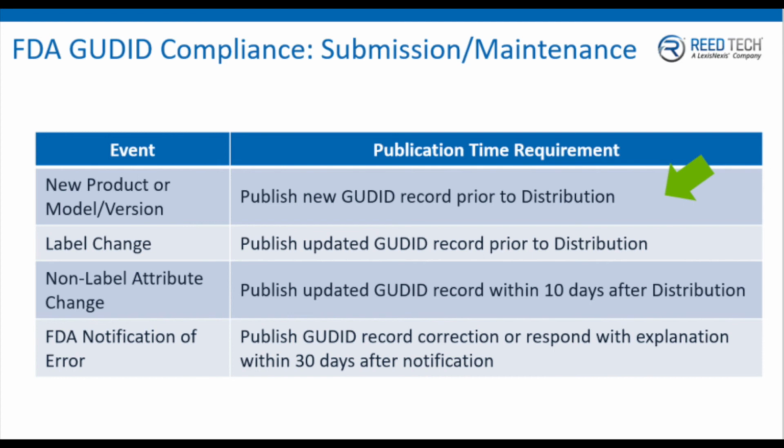And the third major note here is that in the event you distribute your product in a retail environment and make use of a UPC on your particular label, then that particular UPC identifier can be used as a device identifier and serve as the UDI. No direct marking is required for those particular devices in retail, but you still do need to make a report to the FDA's GUDID database. So keep that in mind as you look forward to your September 2020 deadline.